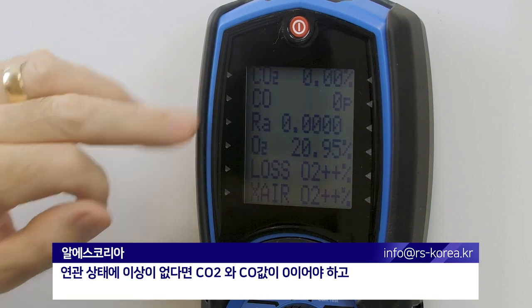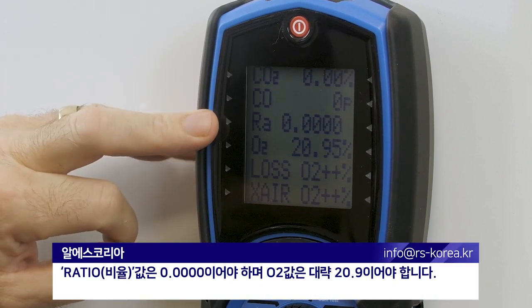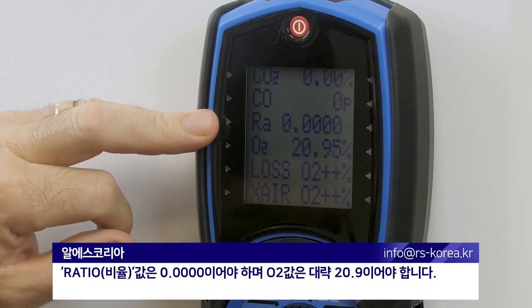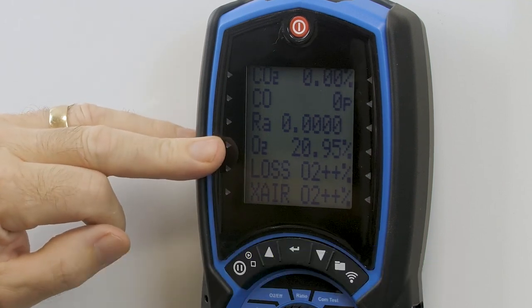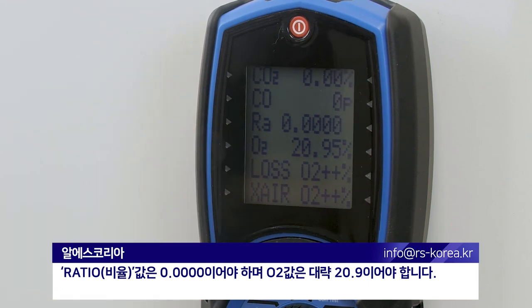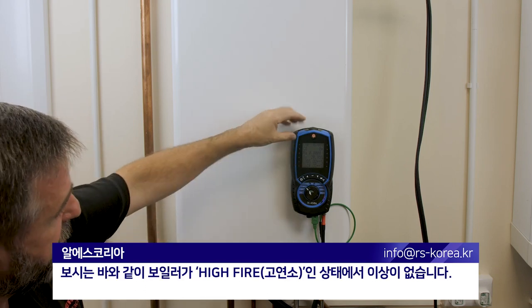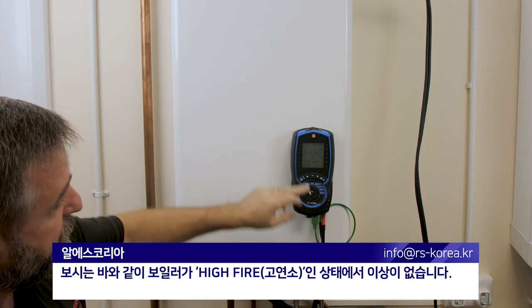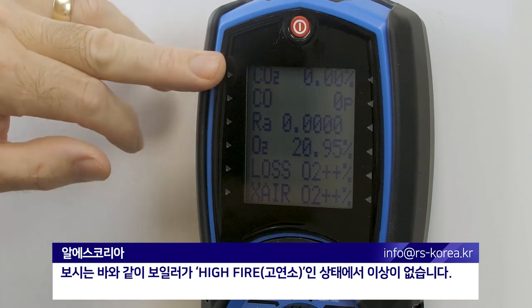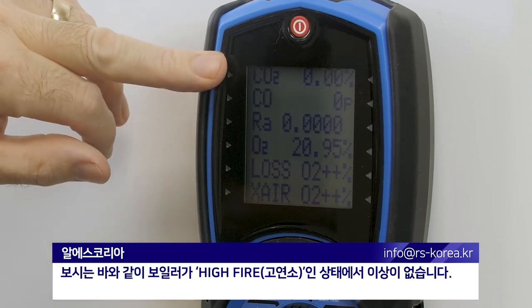Your ratio should ideally be 0.0000 and your O2 at approximately 20.9. And as you can see, with the boiler on high fire, we can confirm that our flue integrity is sound.